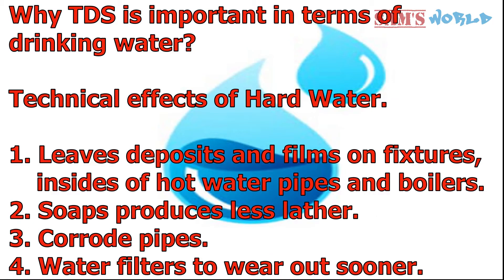High levels of dissolved solids also have technical effects. These solids produce hard water, which leaves deposits and stains on fixtures, and also on the insides of hot water pipes and boilers. Soap and detergent do not produce lather with hard water as they do with soft water. Hard water corrodes pipes and causes water filters to wear out sooner.